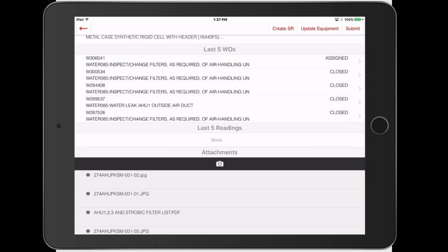So when a work order comes in for too hot, too cold, the technician goes out to the field, chases it back to the source, to the piece of equipment that was causing the problem. They can now scan in that barcode into the reactive for the unplanned work order, and now we capture the history on that. And that's really the sweet spot of having the true cost of what it takes to maintain equipment, because now you get your planned and unplanned work. And having that data is going to allow us to really make informed decisions about what equipment we go after to try to replace.